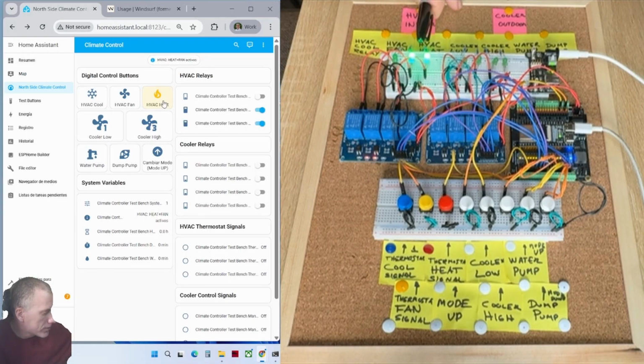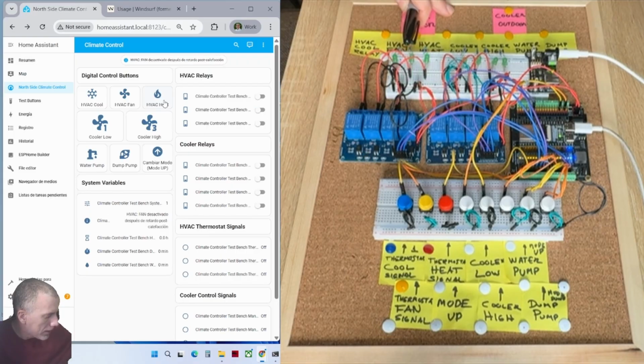If we turn on heat, for example, and then deactivate it, you'll see a delay between the fan and the heat relay, because we need to get all the heat out of the system. When I deactivate it, the fan stays on and later turns off. This delay is completely customizable.